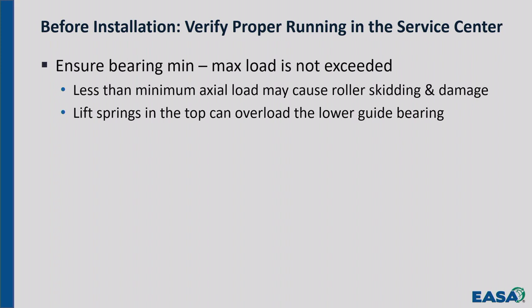That's one of the concerns that come up for test running the motor in the service center, or on site, if they put that motor on site and they run it, and maybe they're doing the installation, you're not doing the installation, and they don't know about that, and they just go and run the motor for 20, 30 minutes or an hour or a day. Okay? And they ruin the lower bearing. Okay? You wouldn't know that.